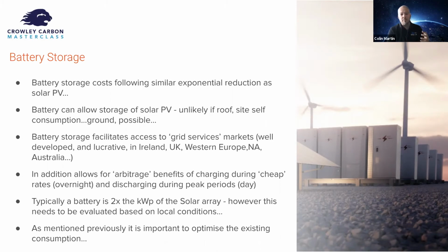This is a rule of thumb as well. If you're putting in a solar PV, the battery starting point should roughly be twice the size of your kilowatt peak array. So if you're putting in a megawatt, 1,000 kilowatt peak solar array, your starting point for consideration of battery should roughly be double, 2,000 kilowatt hour. Again, that's dependent on local site conditions and an actual survey and understanding of your exact requirements. But as a starter for 10 rule of thumb, that's what we would recommend.